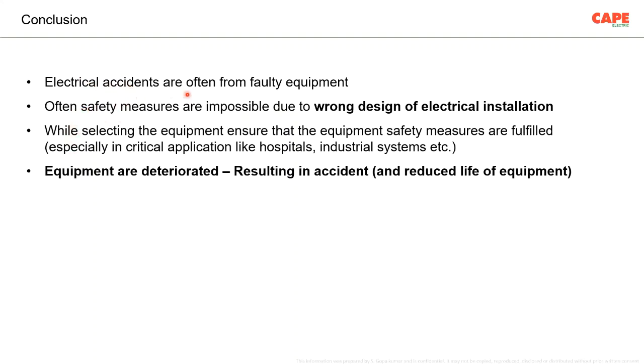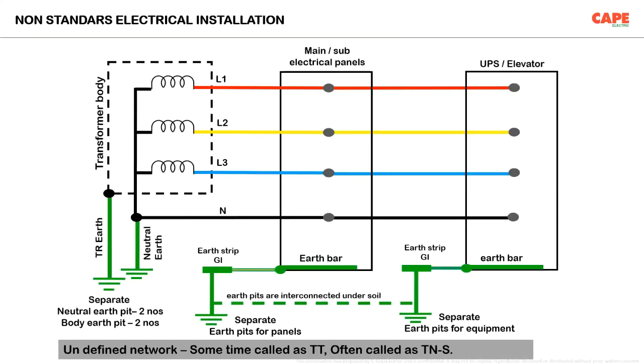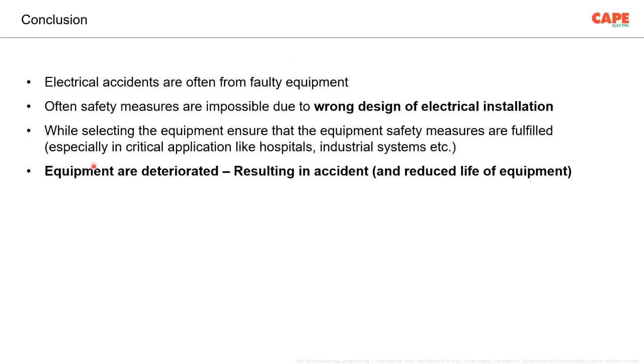Often the failures or the accidents are due to faulty equipment. Often safety measures are impossible due to wrong design of electrical installation. As I said, one of the classic examples of wrong design is that separate unclassified or undefined networks are used all over India. Recently, I even saw an installation. There are so many earth pits in the factory, and around each earth electrode in the soil, they have made a metal barricade. They claim that they are making additional safety for the earth electrode so that people are not going near it and nobody is touching the electrode. So these undefined networks, of course, are a danger.